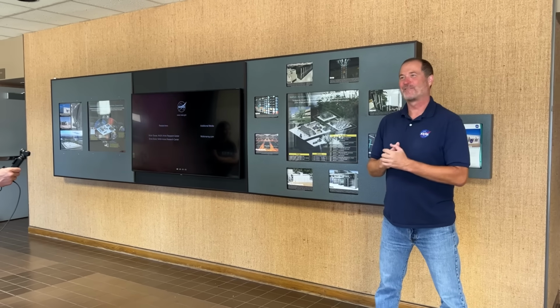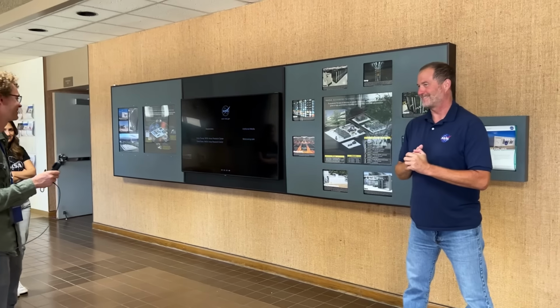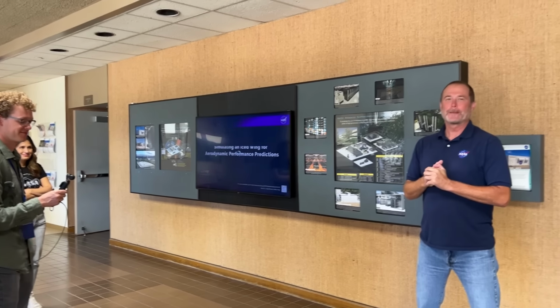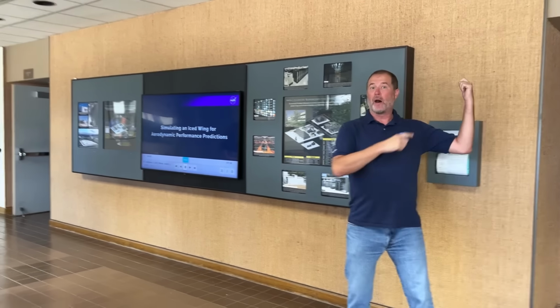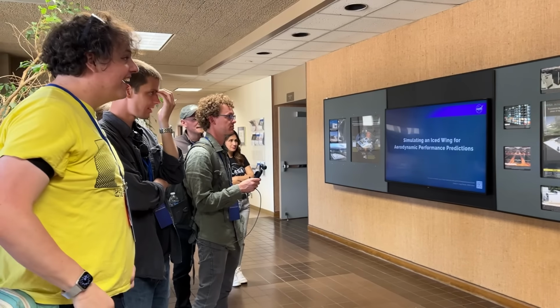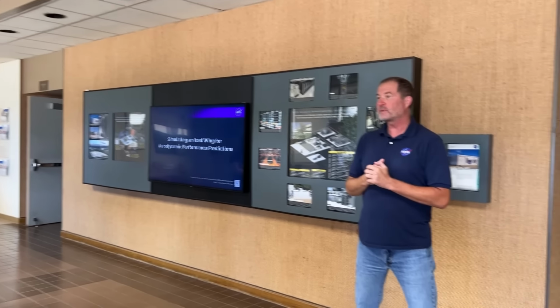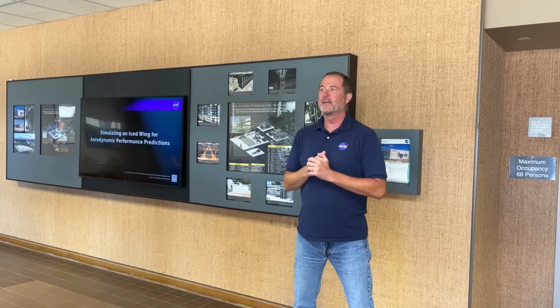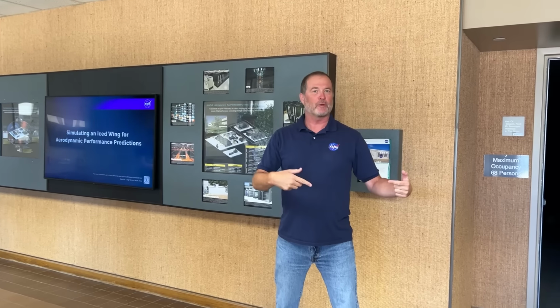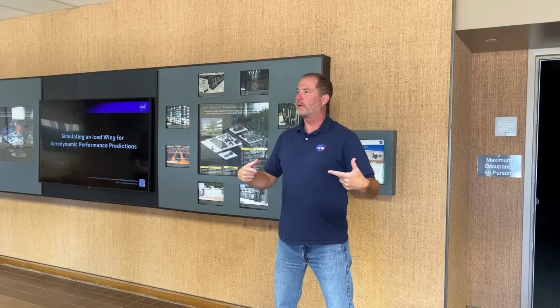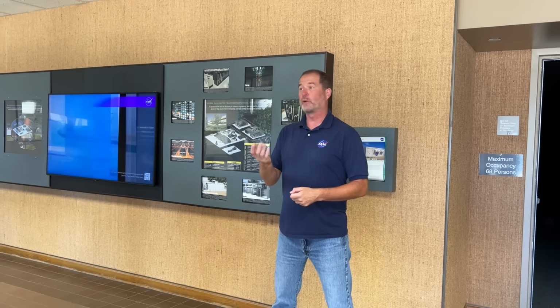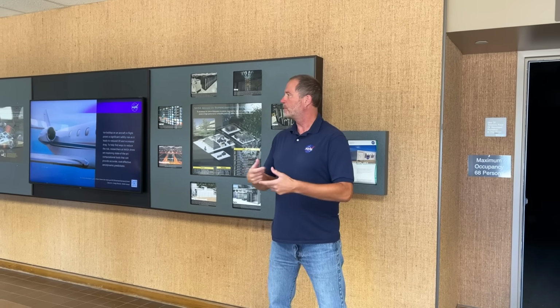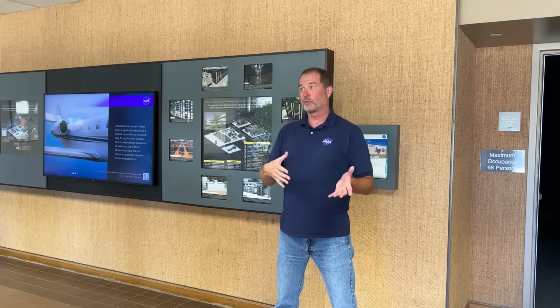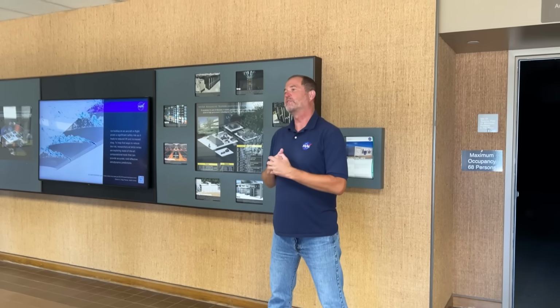Yes. On the back side of this building, we have three RUPS, rotational UPS. We pull power from the grid and put it into a flywheel, which has some parasitic draw, so we lose a little bit there. If utility goes down, the momentum, the energy in the flywheel, gets us through until the generators kick on.